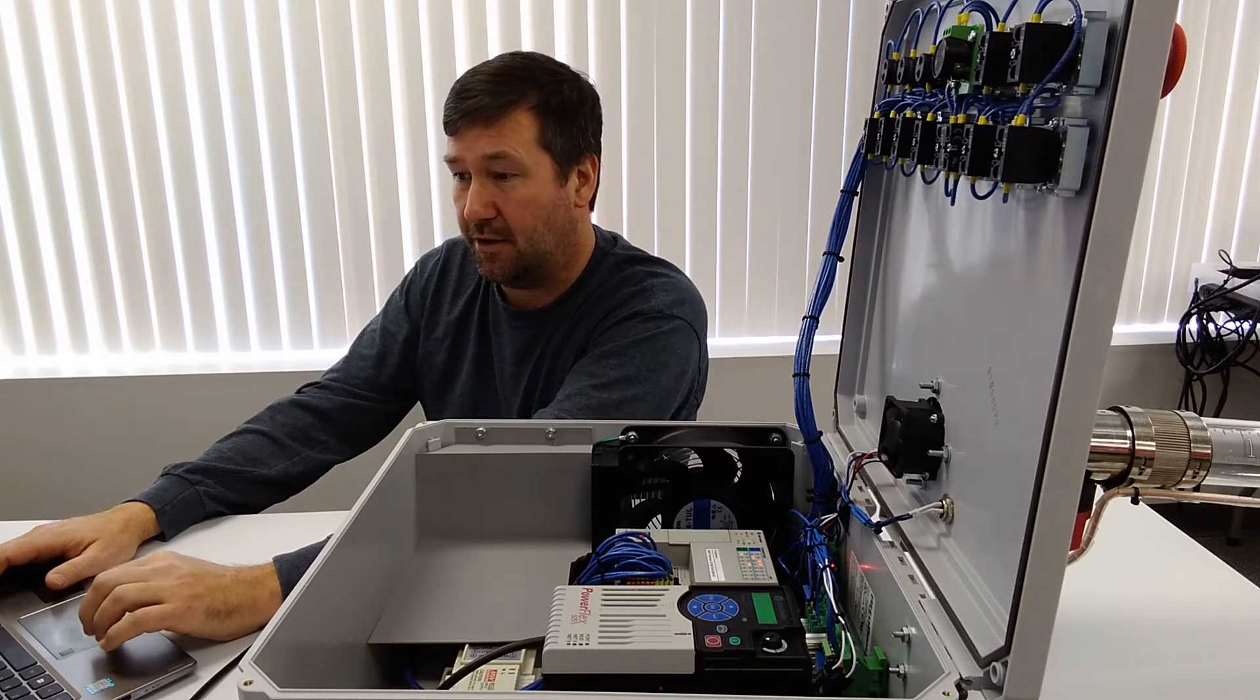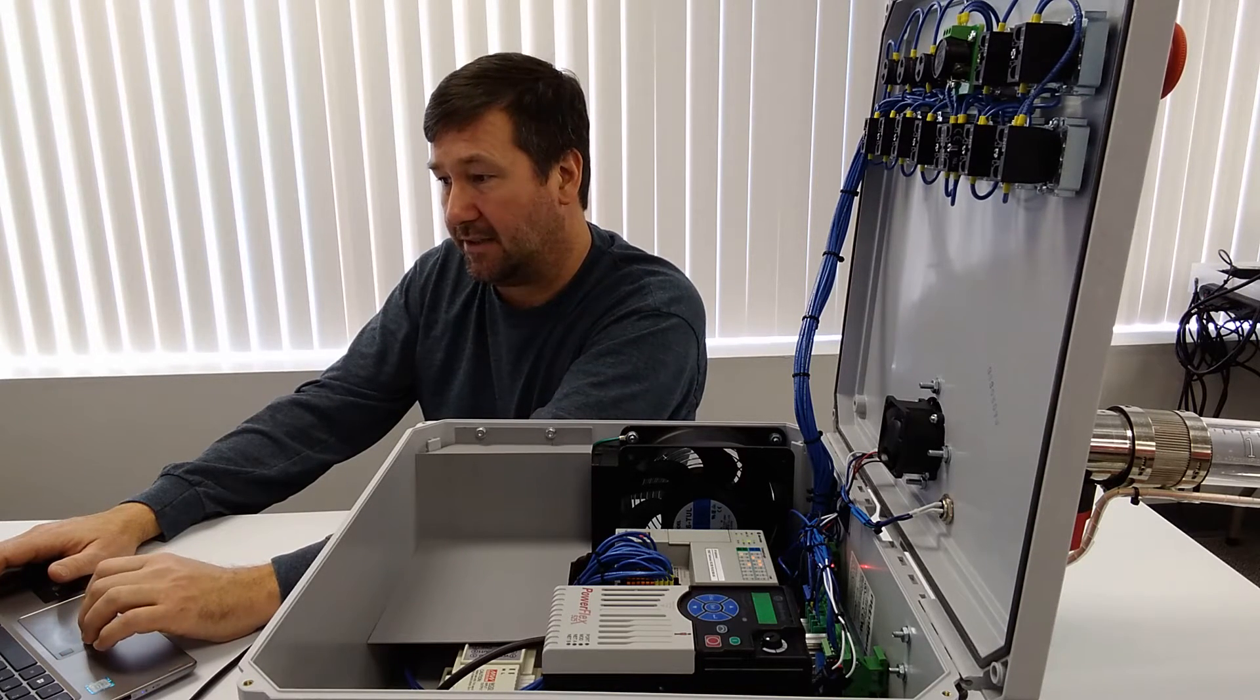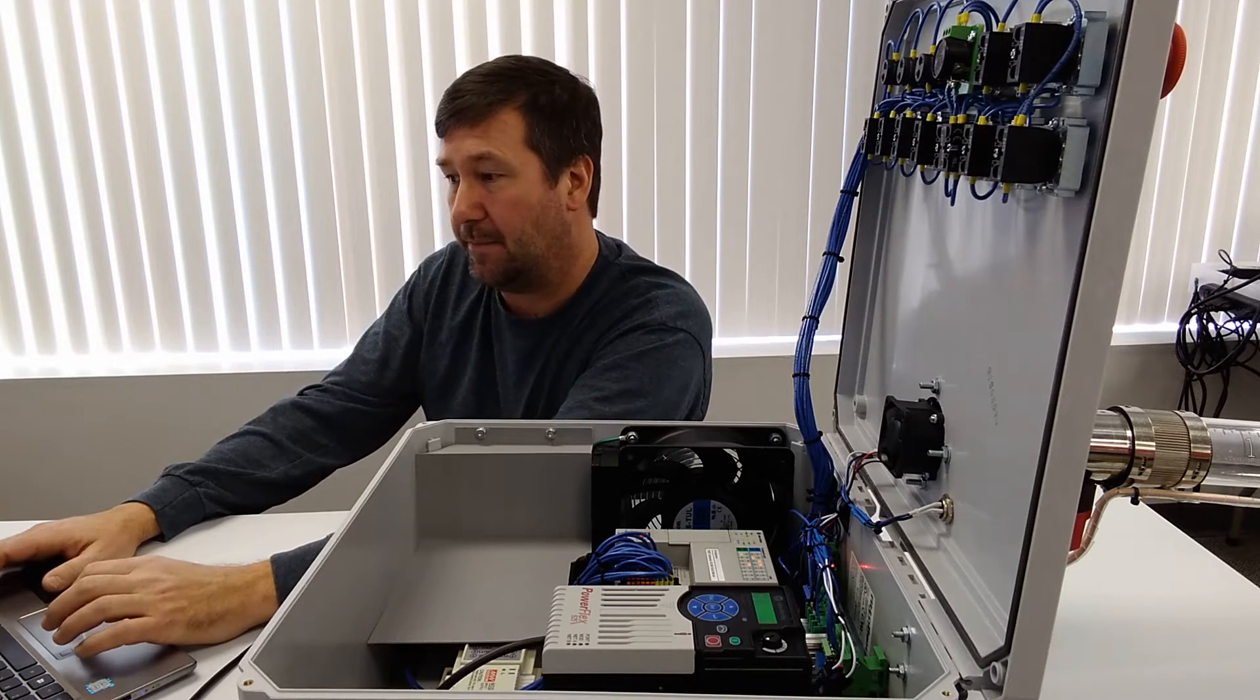Now that I have it back open, right up here we can see it says 32.11, and that is the version that I wanted. So now I'm going to go to Communications, Who Active, and I'm going to find my PLC and click the Download button. It's not going to give me the option right now to download because I need to update my firmware, even though I'm actually downgrading. And yeah, now it is going to allow us to download our program.